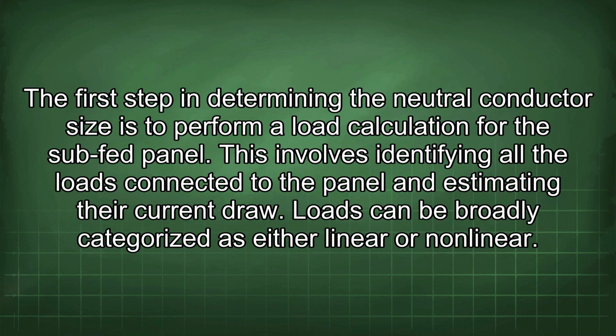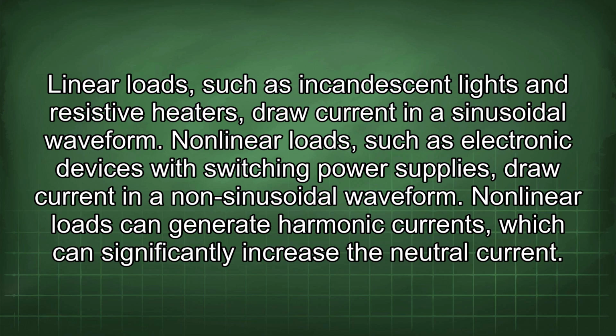The first step in determining the neutral conductor size is to perform a load calculation for the sub-fed panel. This involves identifying all the loads connected to the panel and estimating their current draw. Loads can be broadly categorized as either linear or non-linear. Linear loads, such as incandescent lights and resistive heaters, draw current in a sinusoidal waveform. Nonlinear loads, such as electronic devices with switching power supplies, draw current in a non-sinusoidal waveform. Nonlinear loads can generate harmonic currents, which can significantly increase the neutral current.